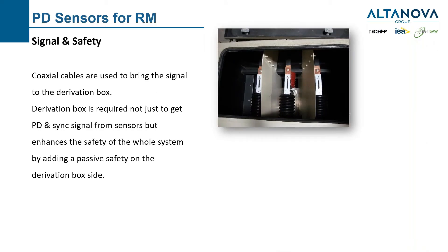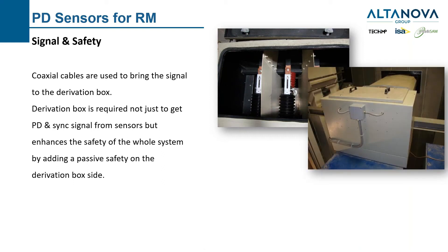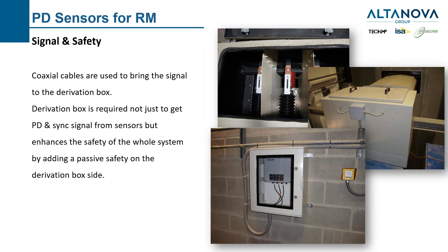Since we cannot access the PD sensors directly once installed in their particular environment, the signals from the sensor must be carried outside with proper conduit and trunks, and made available at an external derivation box. Our derivation boxes provide two things: one is the synchronization signal from one of the phases, and the other is safety for the acquisition unit and the operator. There are voltage controls in the derivation box in order to work in very safe conditions. This allows us to make the test without special permits or working risk assessments, giving us the chance to test the generator whenever we want without big problems.